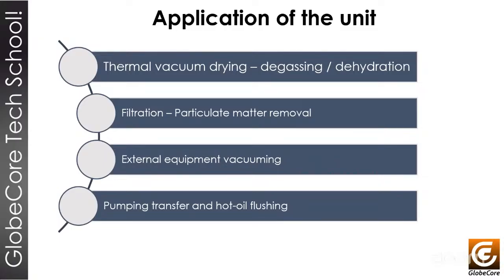The machine can be used for purification of contaminated oils to remove water, free and dissolvable gases, and for heating and drying the oil-filled electrical device with hot transformer oil by thermal vacuum drying. The machine also removes particle matter by means of the high-performance filtering element. The machine is used by installation, repair, and maintenance companies that engage in mineral oil processing and purification. The machine is not for use in explosive, toxic, or reactive media.